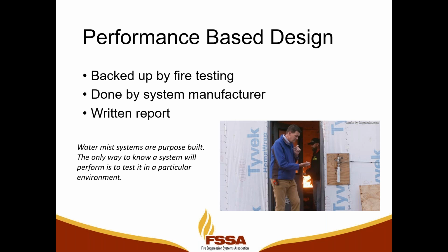We are not designing to achieve a particular water density for a particular type of combustible as we would with a sprinkler system. With a sprinkler system, if you're protecting this type of combustible, you can look in the NFPA, I think it's NFPA 13, and it will tell you you have to achieve this water density, and you design your system to do that. That is not how water mist systems work. With a water mist system, it's proven by doing it, and the design principles are determined by having successfully extinguished fires in those types of environments.